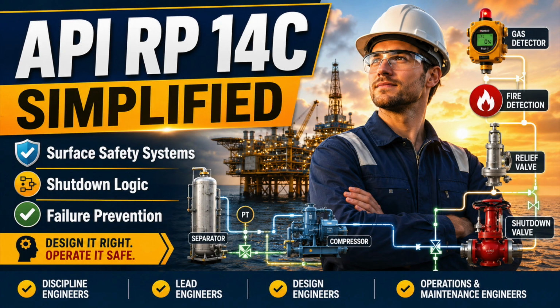Design maintainability into the plant. Provide access, test connections, manifolds, calibration points, safe isolation, and practical removal space. A device that is difficult to test will eventually be tested less often. A detector requiring scaffolding for routine calibration will develop backlog. A level switch that can only be tested by upsetting the entire process will become operationally inconvenient. Poor maintainability becomes permanent risk.